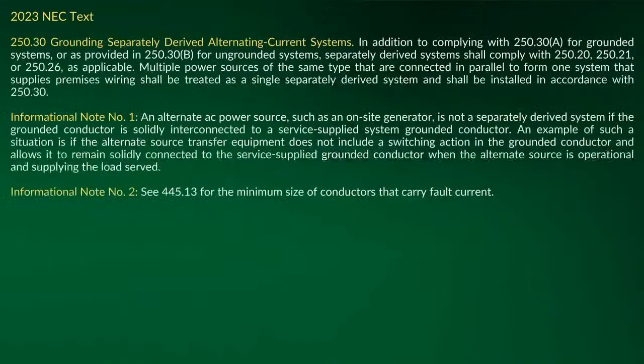Well, if it's being switched, how am I grounding at that transfer switch? It's got to be ahead of it. Yeah, that's what I'm saying. You've got to look at other installations that could affect the way that you set that system up. And it's regardless whether it's 3-wire or 4-wire, that doesn't matter.